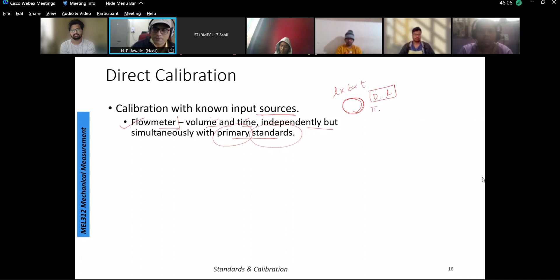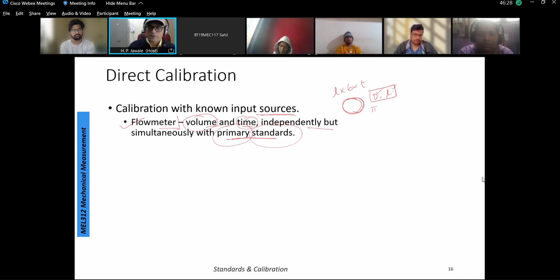So what is the volume? It is length into width into thickness, a normal way, or if it is a round element flow meter having the round pipe, there will be the diameter and the pipe length. So these may be the entities for volume measurement. So it will be, say, pi by 4 d square into L for measurement of volume, and for measurement of time there will be one element. So we measure diameter and length by means of the vernier caliper or screw gauge. So what we do, we measure these independently but simultaneously with whatever better accurate standards are available with us, say primary standards. Calibration with the devices having accuracy equivalent to the primary standard gives similar accuracy.